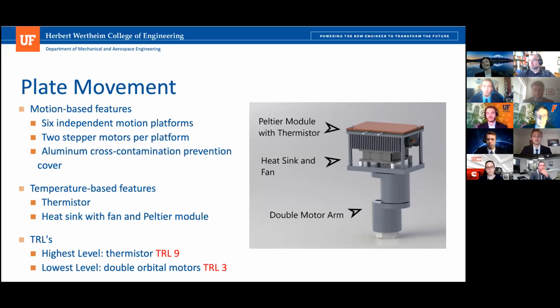So if we were making the top cold, the bottom would be warm, and we would be able to wick away some of that heat to make it cooler on the top. In between the copper plate and the heat sink, we also have insulation, to make sure that we have efficient cooling or heating on that top well plate cover.